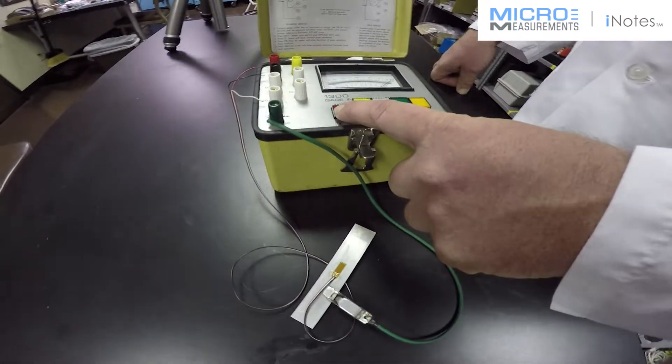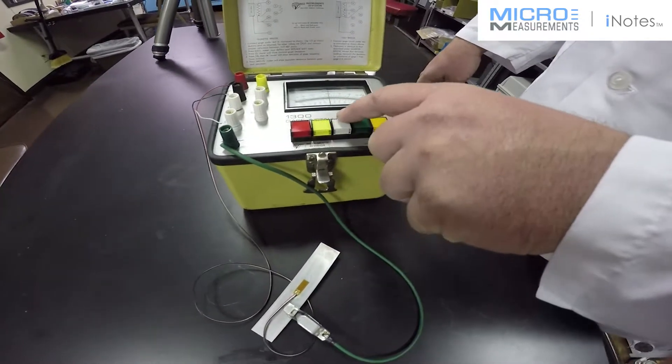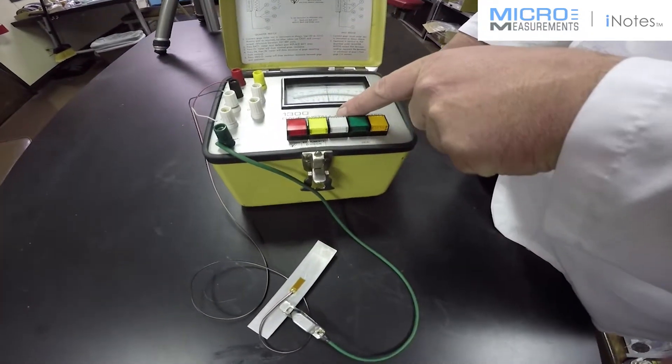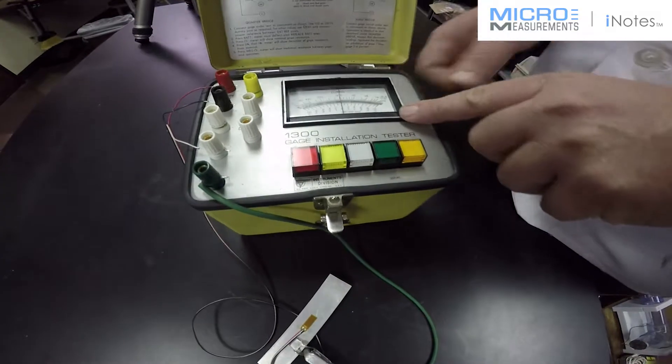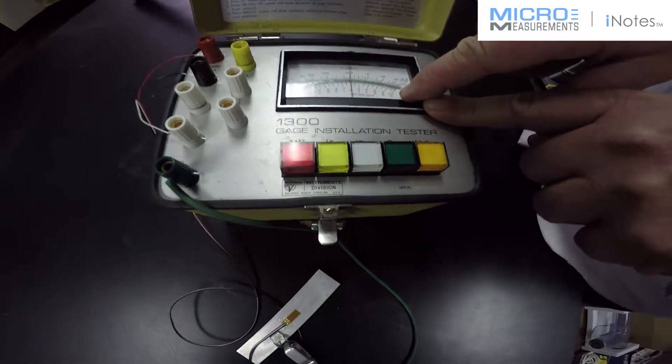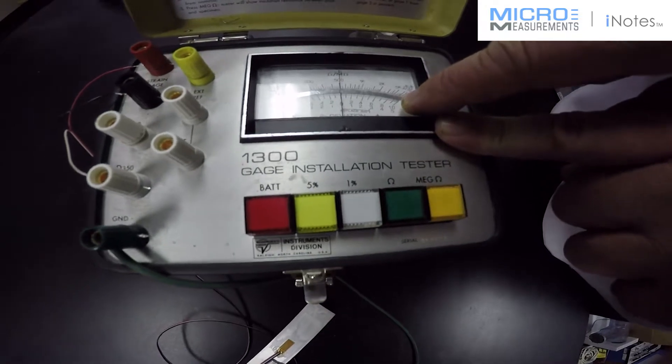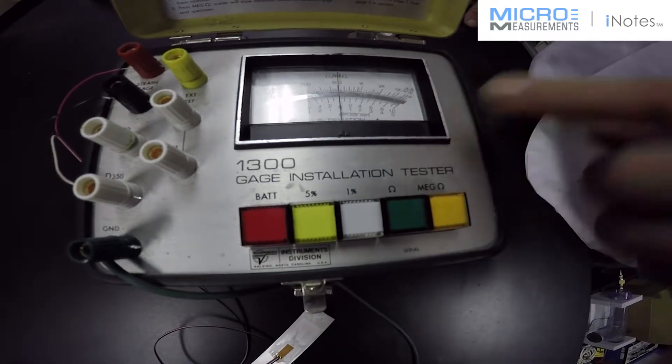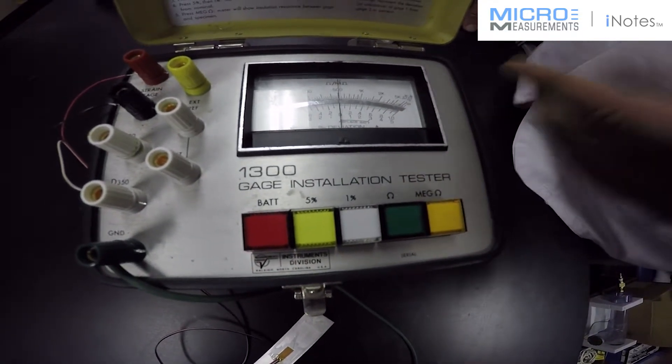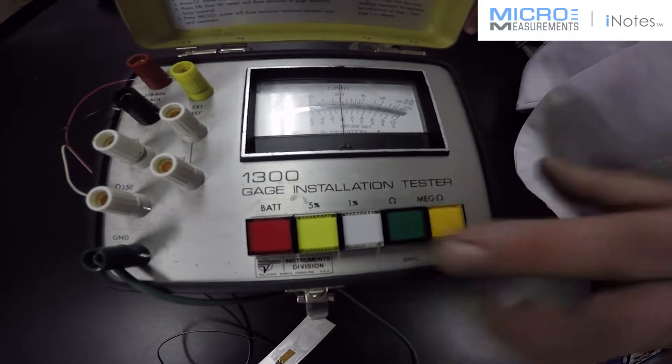I'll show you how you can QC a strain gauge with this. Basically, first we want to make sure our battery is working. Second, this is a 5% range and a 1% range. So, looking at the scale, the 5% range is at the bottom, the 1% range is the next one up. This is just going to tell me the tolerance - how close to 350 is my strain gauge?